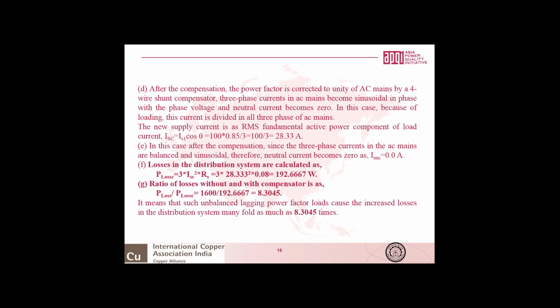And in this case, after the compensation, see the 3-phase currents in the AC mains are balanced and sinusoidal. Therefore, neutral current becomes 0 as ISNC equal to 0. The losses in the distribution system now are calculated after the compensation. P loss C, that's for the compensation, equal to 3 into ISC square into RS, putting the values of current and resistance. We get the losses 192.67 watt. So now these losses are reduced from 1600 watt to this value of 192.67, or 193 watt.